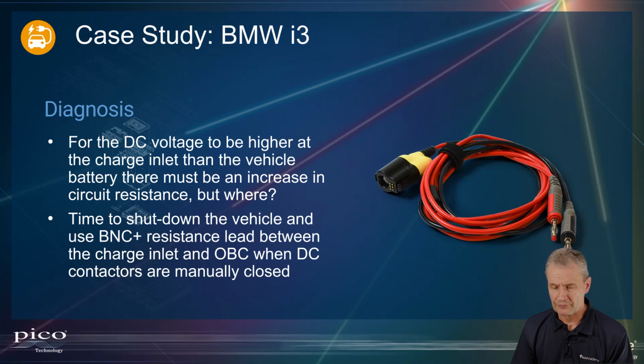Now, at this point, we'll do this live. We've actually got the onboard charger off the vehicle. We'll do a simulation of the test that we actually did on the vehicle and see what the values are. Remember, when measuring resistance on anything carrying high current, we really want to be down in the milliohm range, because any debris on those contacts will be revealed with the milliohm meter. Anything above, say, 2 milliohms across the contactors is cause for concern, since we want a good clean contact there. So we'll do that now live, and then we'll come back to what was actually wrong with this vehicle.